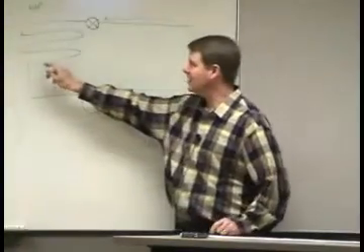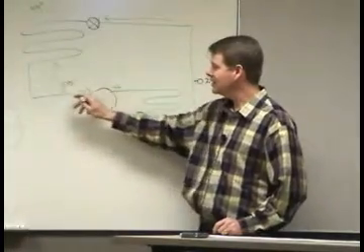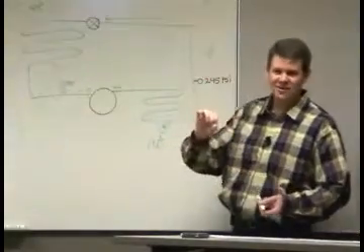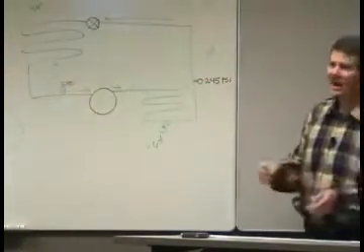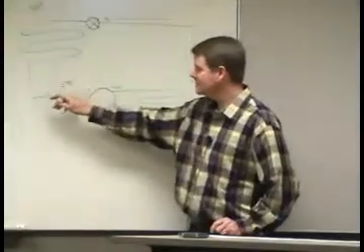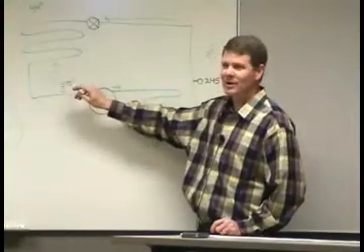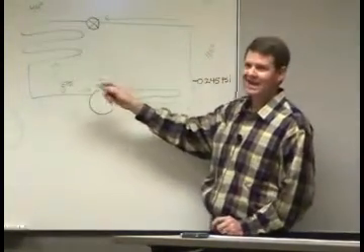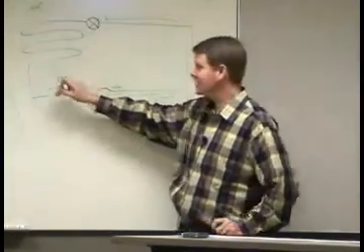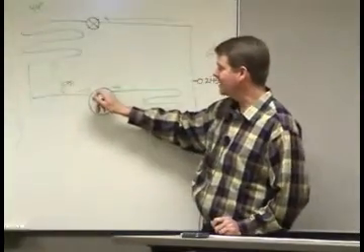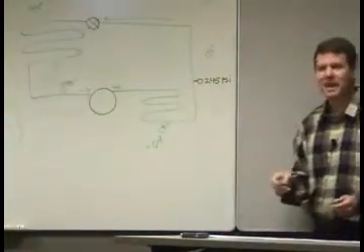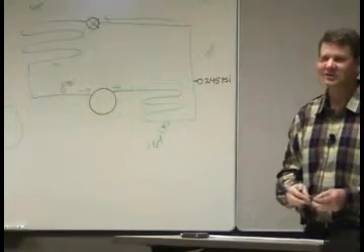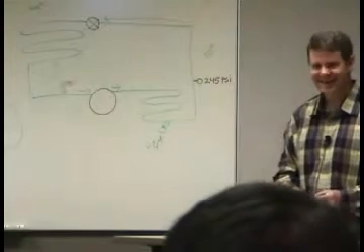So what happens there is, if you come out to your compressor and look, and this line out here is a big chunk of ice coming all the way back, that's because you've got liquid coming all the way back here, and it's trying to boil at 44 degrees, and it can't find any heat to boil with. So it's going to keep trying until it gets all the way back. If liquid makes it back to the compressor, those valves, that suction valve on the compressor won't last long.